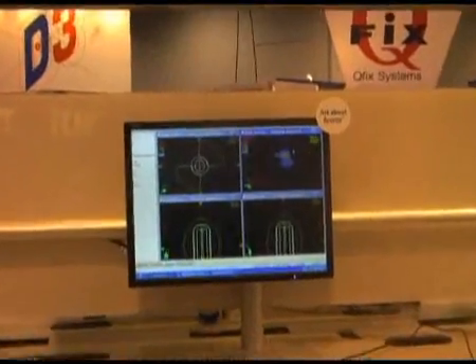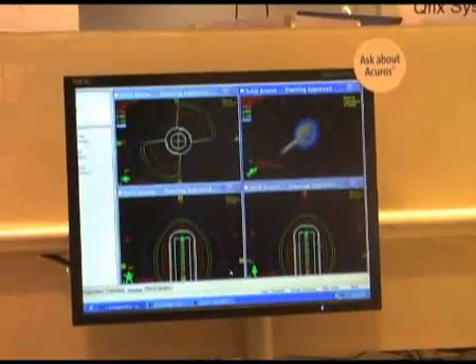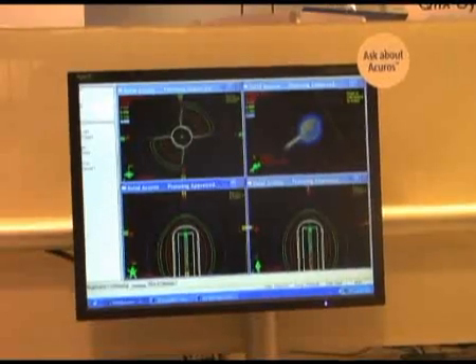Our newest development is a product called Acuros, which actually improves the dose accuracy of brachytherapy. It was released several months ago. We just got 510(k) approval on it, and it's been a very hot topic at the show at AAPM.